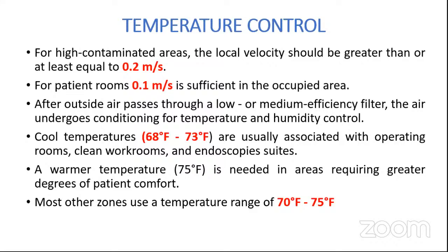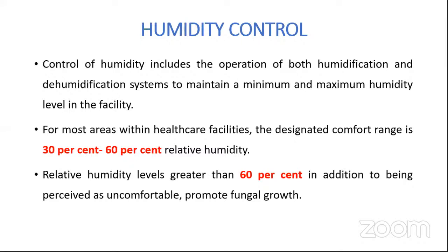When we talk about temperature control, the local velocity should be at least 0.2 meter per second. For a patient room, it should be 0.1 meter per second. Cool temperatures are to be kept for areas which are operating rooms, clean workrooms, and where we conduct operations, the operation theaters. So the temperature range that we look forward to is 70°F to 75°F. The humidity, yes, is of more importance when we are talking in terms of healthcare units. The humidification and dehumidification systems need to be maintained at different levels in the facility. We consider 30 to 60% to be a very good range for managing the relative humidity in a facility. Anything greater would add to the problem, as it can promote fungal or mold growth.